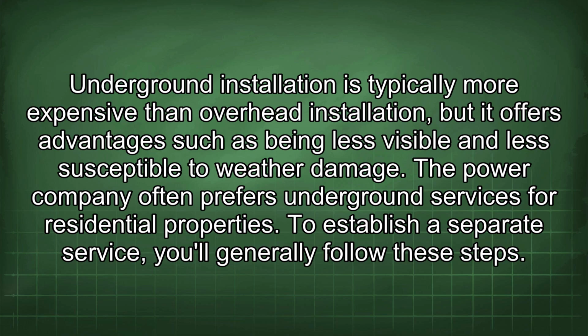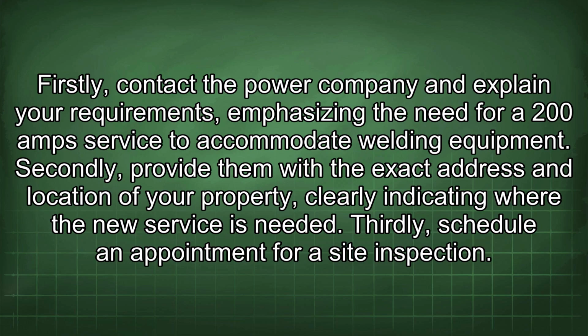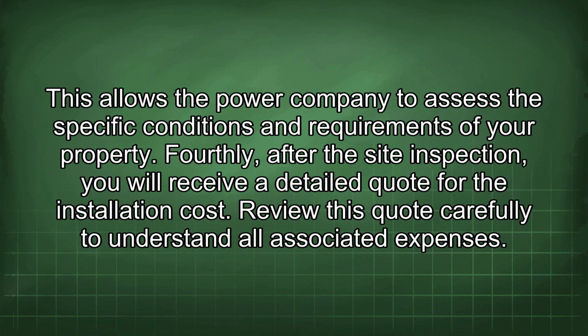To establish a separate service, you'll generally follow these steps. Firstly, contact the power company and explain your requirements, emphasizing the need for a 200 amp service to accommodate welding equipment. Secondly, provide them with the exact address and location of your property, clearly indicating where the new service is needed. Thirdly, schedule an appointment for a site inspection. This allows the power company to assess the specific conditions and requirements of your property.